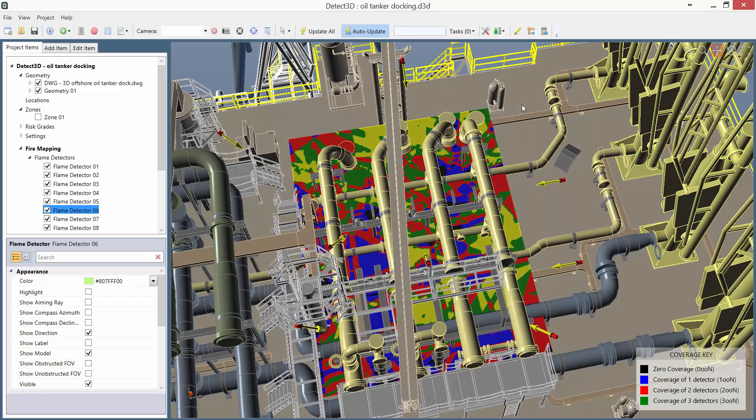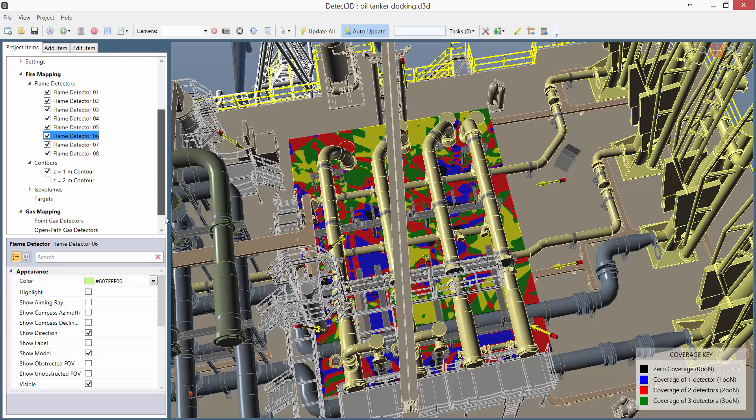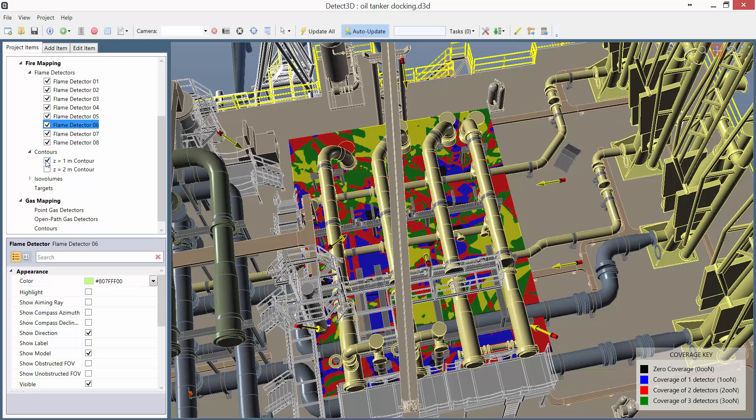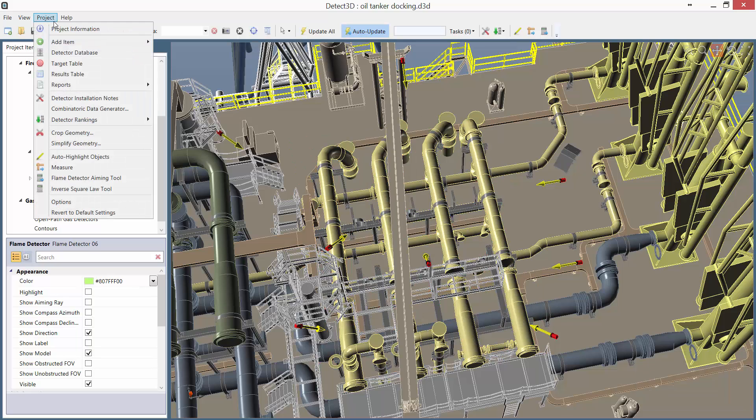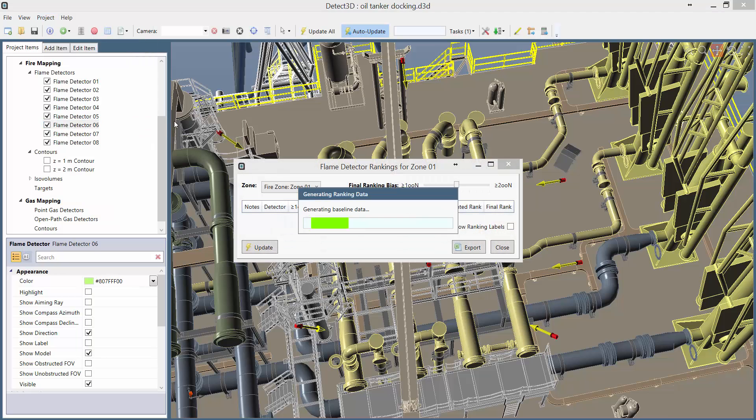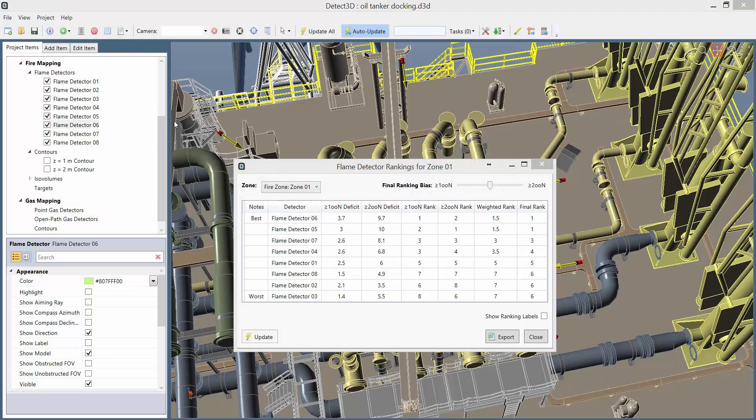Overall we've got a pretty good layout, but the question really is do we actually need eight detectors to cover this zone, or can we get equivalent coverage with fewer detectors? To answer this question, I'm going to use the detector ranking tool, which is accessed via the project menu where I can select my fire zone. When the ranking tool loads, it generates a large data set by instantaneously switching off each detector in order and calculating the effect it has on coverage.